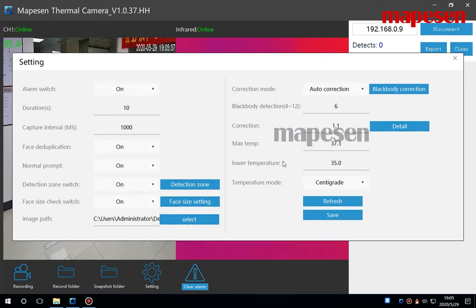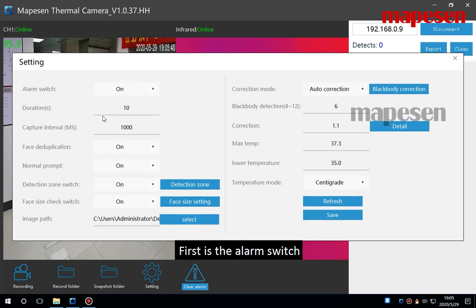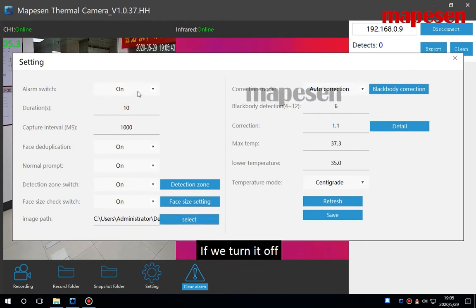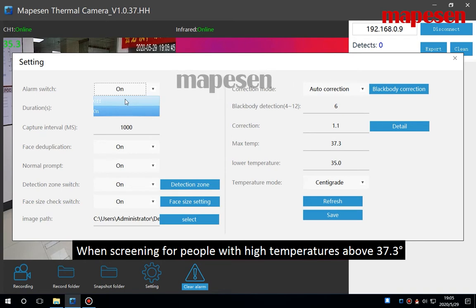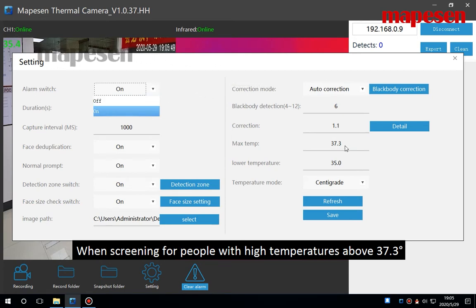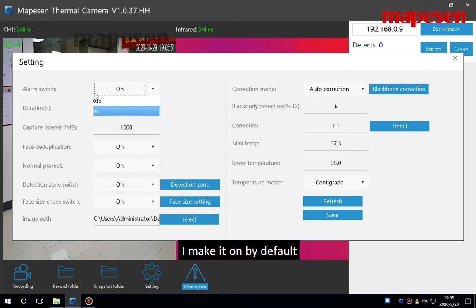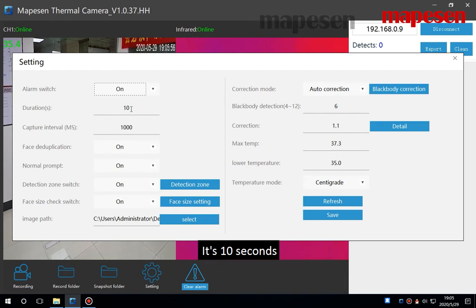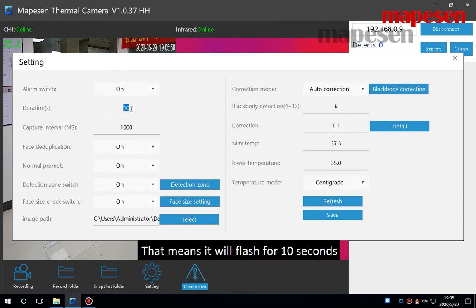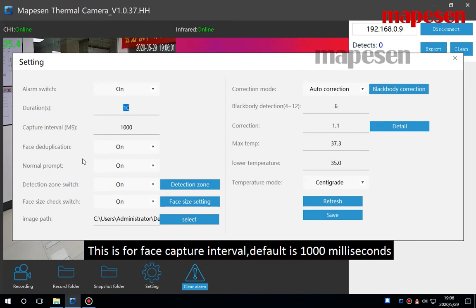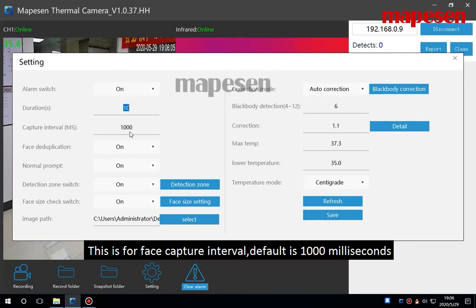Let's look at this parameter settings. First is the alarm switch. If we turn it off, when screening for people with high temperatures above 37.3 centigrade, it will not alarm. I'll keep it on by default. The second line is the time of the alarm. It's 10 seconds, that means it will flash for 10 seconds. This is for face capture interval, default is 1000 milliseconds.